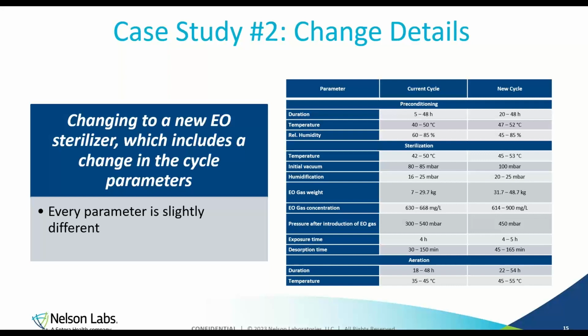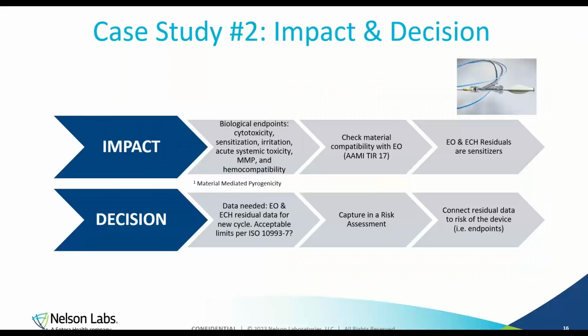And you may be thinking, I thought I joined a biocompatibility seminar, not a sterilization seminar. But remember that one of our risk factors that we need to look at is processing. And we know that EO can have a biocompatibility impact. So that's why we want to assess this, not only because you would need to repeat some of your sterilization validation work to approve this next supplier, but we also have to think about any impact from the biocompatibility portion to the patient.